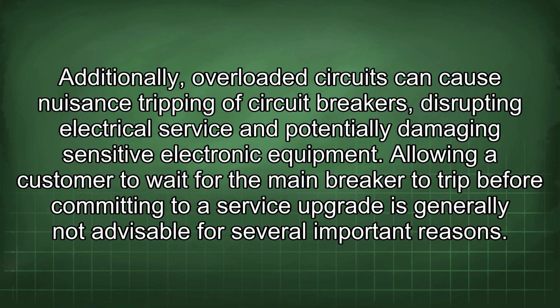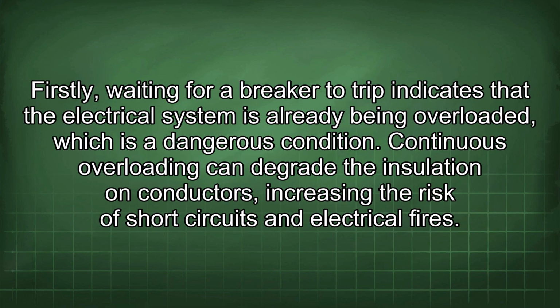Allowing a customer to wait for the main breaker to trip before committing to a service upgrade is generally not advisable for several important reasons. Firstly, waiting for a breaker to trip indicates that the electrical system is already being overloaded, which is a dangerous condition. Continuous overloading can degrade the insulation on conductors, increasing the risk of short circuits and electrical fires.